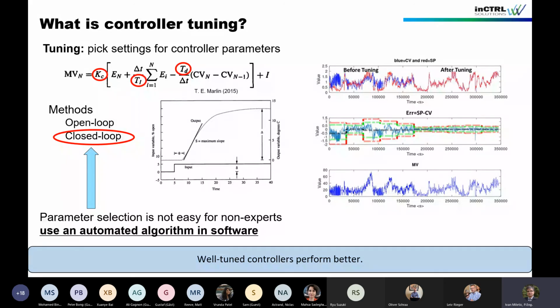Before tuning, you see that the blue line is not able to track the red line very well. There's lots of variability, and lots of offset and difference between the red and the blue. When you look at the effect of tuning after you apply it, the controller, in this case a PI controller, is much better able to track the set point over time.